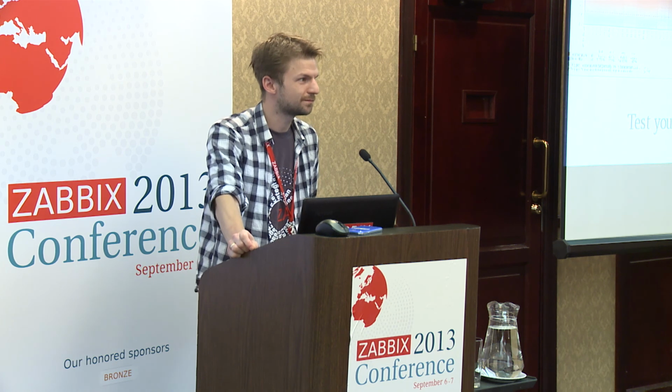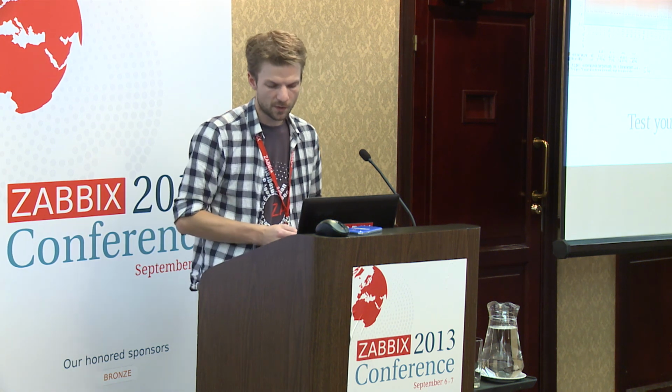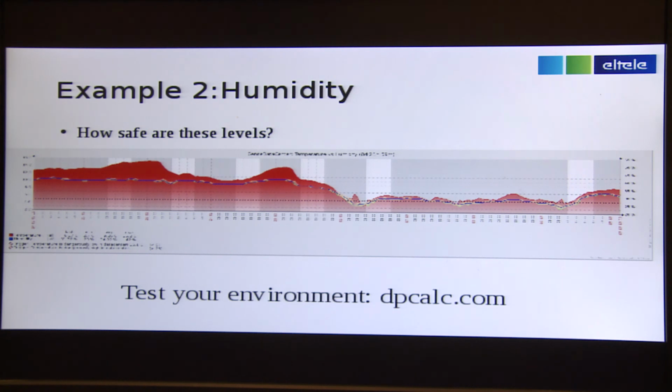So quick question, we're lying here at closely 40% humidity and 10 degrees. So, are these levels safe? Well, the part about non-condensing on the technical specification is vital. Anything above 95% is condensing, period. So that's fine, but it says 5 to 95. But condensation happens when heat meets cold with a perfect amount of humidity combined.